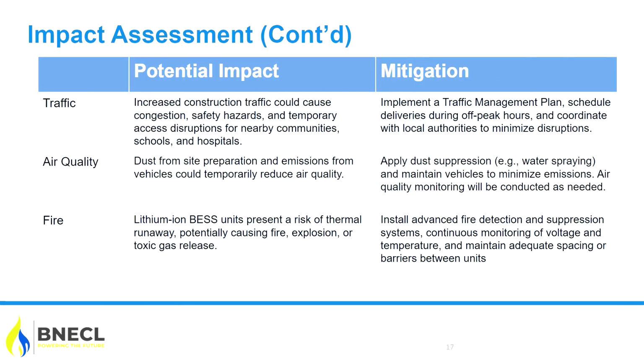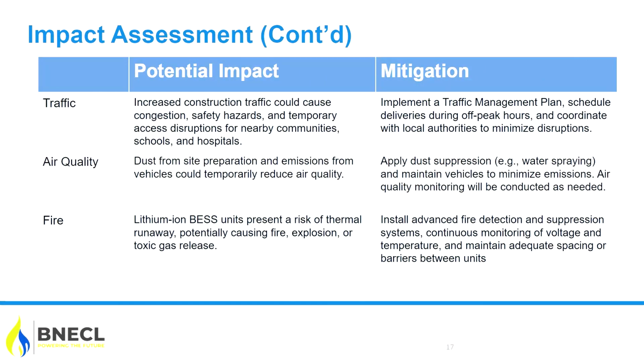Risk of fire was also identified as a potential impact, primarily relating to the batteries themselves. Mitigation includes early fire detection and automated suppression systems supported by thermal management systems, physical containment with appropriate containerization of the battery energy storage system housed within containers, and adequate spacing and setback with strict adherence to safety standards, primarily the NFPA 855 standard. Rigorous inspection, maintenance, and emergency response protocols will also be necessary.